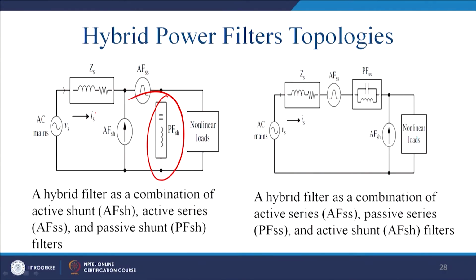Similarly, you can have a left shunt UPQC with a passive filter, generally it is preferred now. I was telling you the task of this entity is to clean up so that UPQC can act better. So you can have this notion, again this can be interchanged, first passive then active, and thereafter we can have a hybrid filter with combinations of the active series, passive series filters and the active shunt filter.